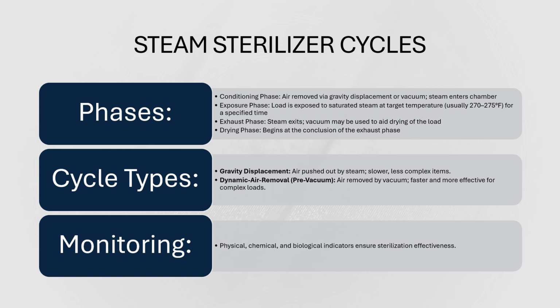So the physical monitoring of it, this is the receipt that is printed out throughout the whole phase. Once it's done, it will finish printing it out. This will stay with the load itself. This is where you will check to make sure the exposure time was met. Make sure the temperature stayed constant throughout the whole phases. You will sign this at the bottom of this receipt. This is a legal document. This stays with your documentation.